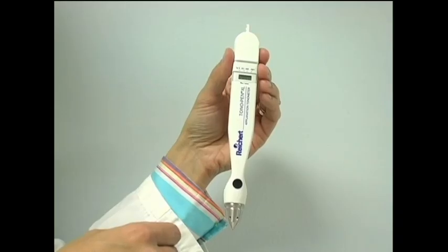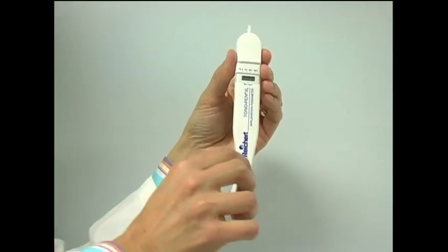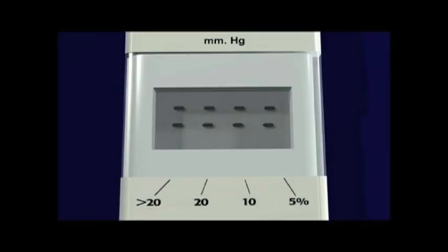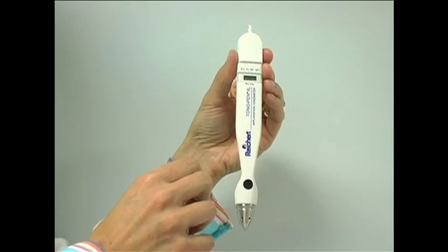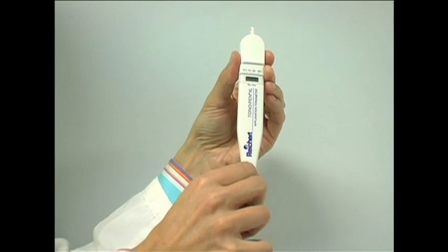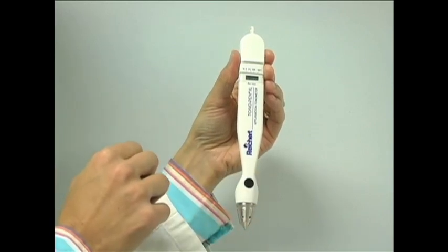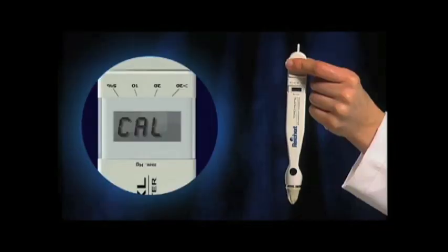To check for calibration, hold the pen straight down and press the operator button once. If you see a double dash line on the LCD screen, you may proceed with measuring the IOP. If you see a single dash line, the tonopen must be calibrated prior to use. To calibrate the tonometer, keep the tonopen pointing straight down and rapidly double-click the operator button. Listen for the beep and the LCD screen will say CAL.